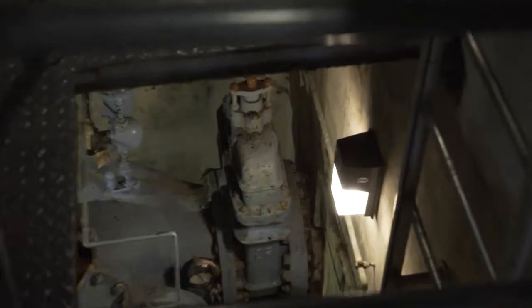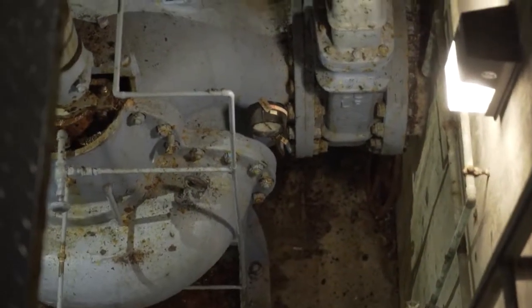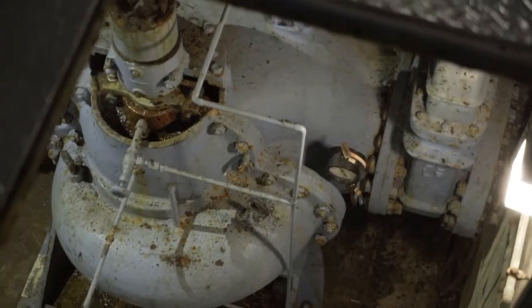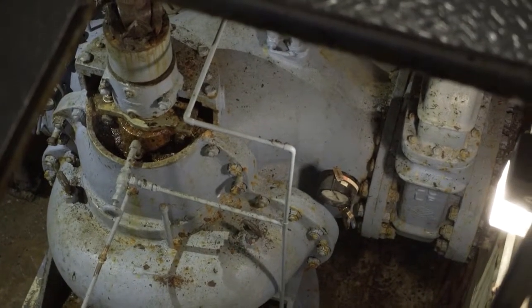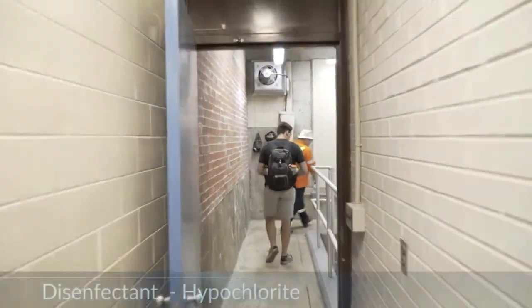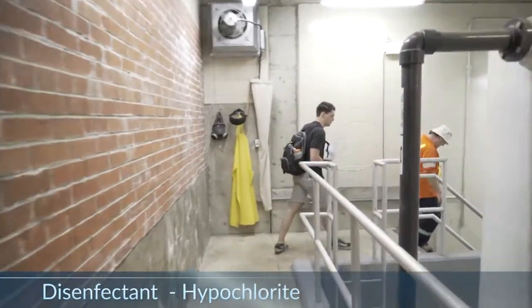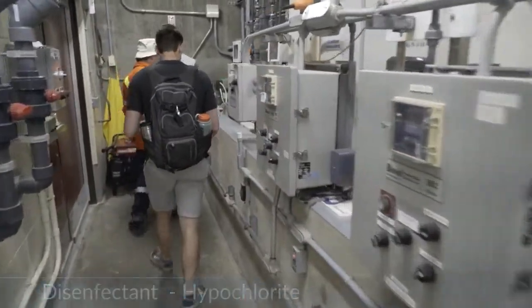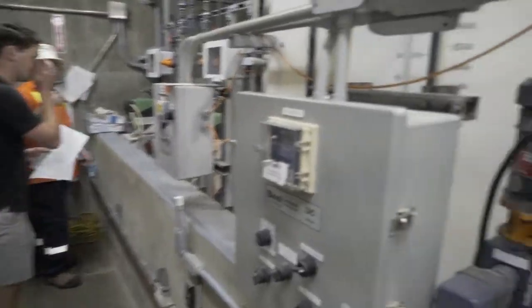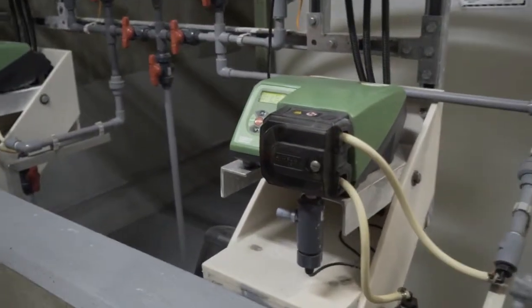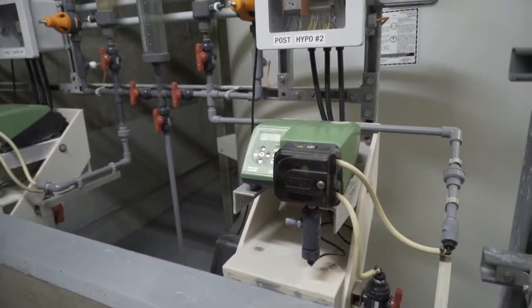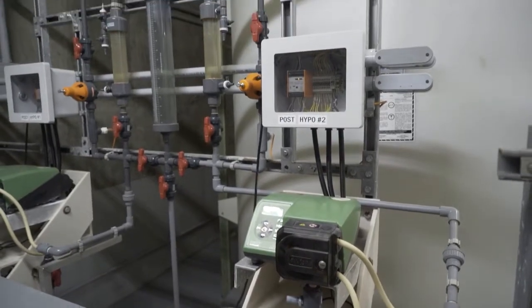Clean water leaves the filters and goes to the clear well. A disinfectant, sodium hypochlorite, is added to the clean water in the clear well. This kills any germs and bacteria from the water. The clear well gives the water the required contact time with the sodium hypochlorite. Clean water is then passed to the high-lift pumps. These large pumps pump the water into the distribution system.